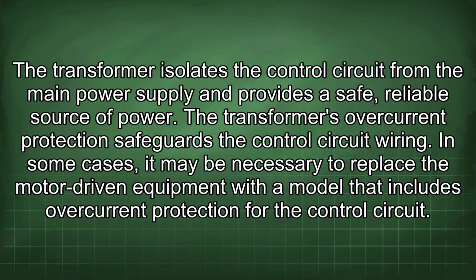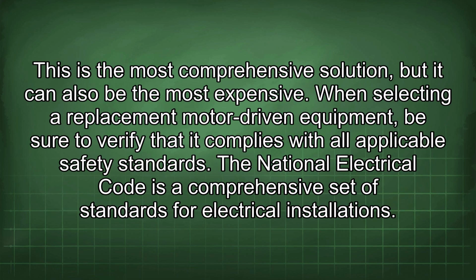In some cases, it may be necessary to replace the motor-driven equipment with a model that includes overcurrent protection for the control circuit. This is the most comprehensive solution, but it can also be the most expensive. When selecting a replacement motor-driven equipment, be sure to verify that it complies with all applicable safety standards.